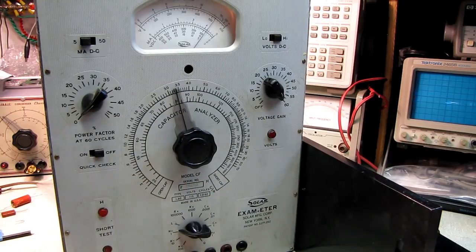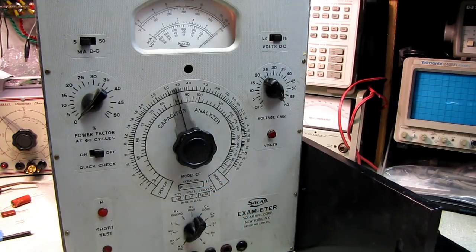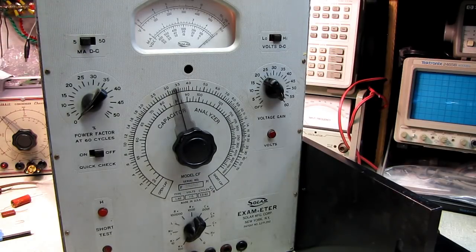Go back to the M times 1. We'll let it charge up until it goes up to infinity. It'll charge quicker because we're passing more current through the meter on the M times 1 scale. And basically, we're almost to infinity. This is M times 10. We're still almost at infinity. That's M times 100. So there is virtually no leakage in that capacitor. It is just virtually perfect.